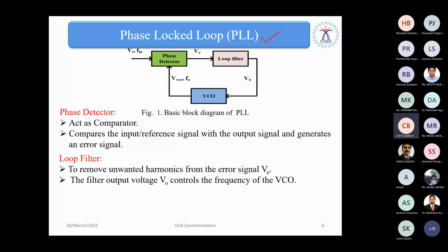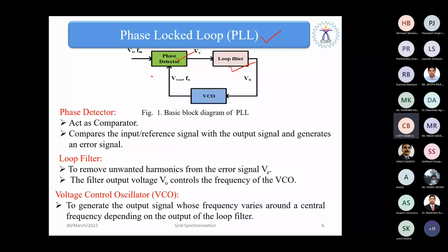And you can see the analog phase lock loop has three important components called the phase detector, the loop filter, and the VCO. The role of the phase detector is that as we feed the input voltage with the corresponding frequency, it detects the phase difference between the actual phase and the estimated phase. It is simply a comparator. It compares the input and reference signal and produces an error. That error is given to the loop filter.